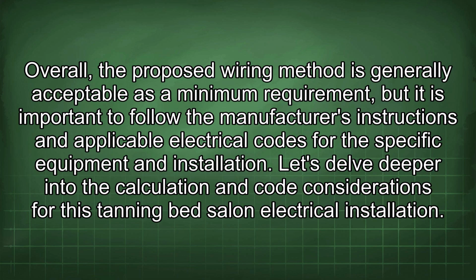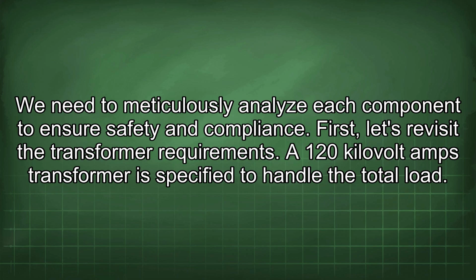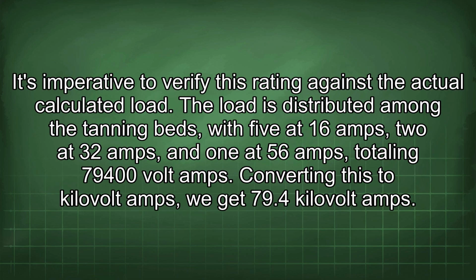Let's delve deeper into the calculation and code considerations for this tanning bed salon electrical installation. We need to meticulously analyze each component to ensure safety and compliance. First, let's revisit the transformer requirements. A 120 kVA transformer is specified to handle the total load. It's imperative to verify this rating against the actual calculated load.